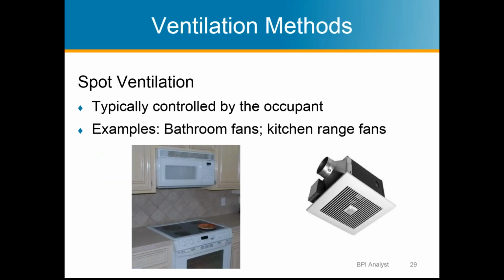These are typically controlled by the occupants, although some fans, and the Panasonic Whisper Greens have these, where you can set them up to where they're on all the time at a low speed. So you could replace, like in an existing home, a bath fan with one of these Panasonic Whisper Green fans, and you could set it up to where it runs all the time, 24/7, and is continuously exhausting the air from the bathroom or the laundry room, or any room, but those would be usually where they're going to be installed. But then when somebody goes in to take a shower and wants more ventilation, they can then turn the switch on and it goes to a higher speed. When the switch goes back off, it goes back to its lower speed.